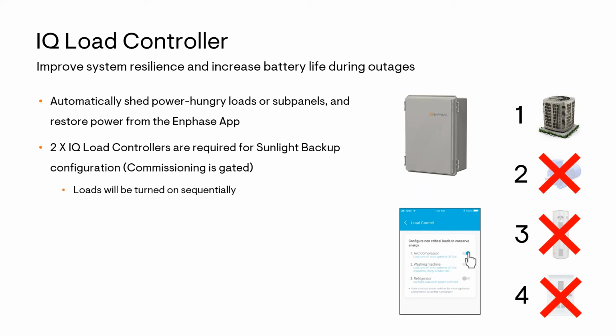Now for the sunlight backup configuration that I mentioned, where you have backup power from the solar inverters without any battery, we require the installation of 2 IQ load controllers. Now please note they must be the Enphase branded and kitted IQ load controller, not one that's built from individual components.